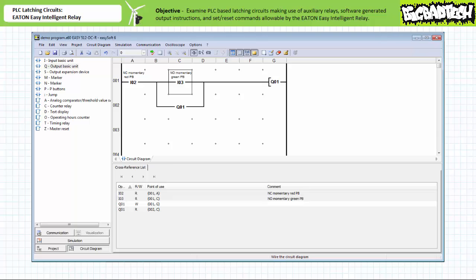Rung one is a series configuration of a make instruction examining input I2, the normally closed red push button, and another make instruction examining input I3, the normally open green push button, controlling output Q1. Rung two is a make instruction examining output Q1 in parallel with the make instruction examining input I3 in rung one. This is the software-generated holding contact, almost directly mimicking the function of an auxiliary contact in an electromechanical circuit used for holding circuit purposes. Using this more streamlined approach, the program is ever so slightly smaller.